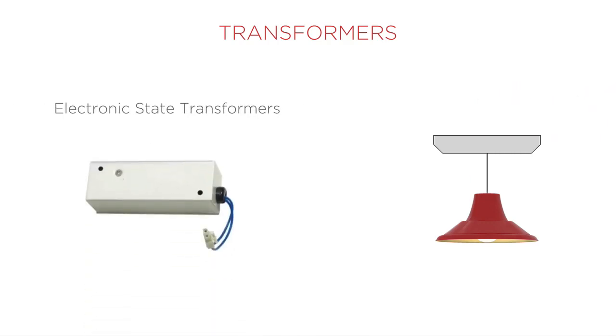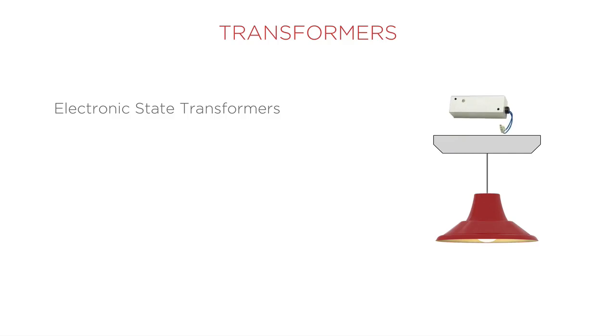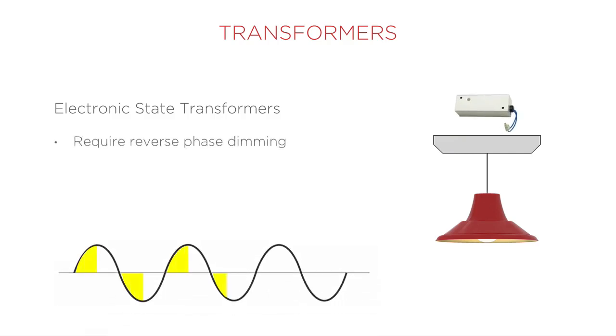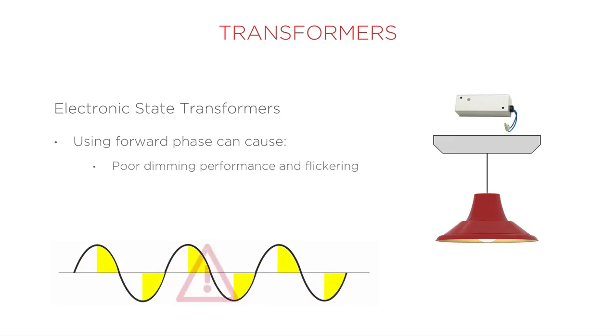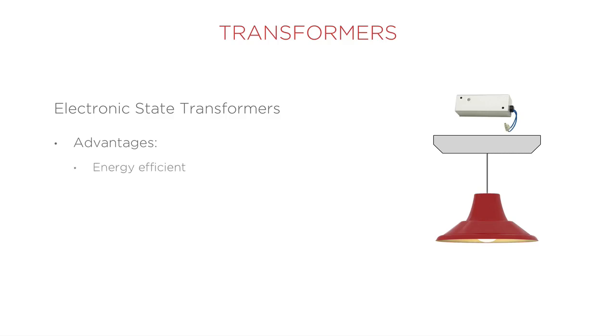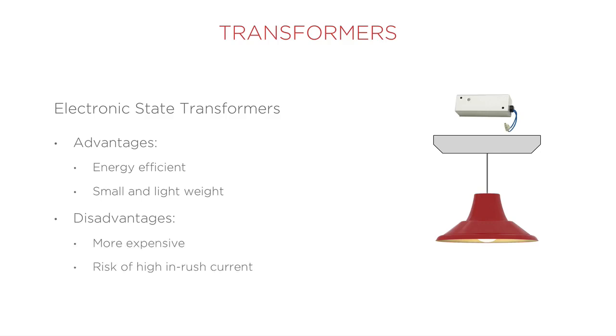Electronic state transformers are the newer type of transformer. They require reverse phase dimming. If used with a forward phase fixture or load, there will be poor dimming performance and flickering, buzzing from the bulb itself, and damage to the dimmer and/or the transformer. It is more efficient, smaller, and lightweight than the older magnetic core transformers, but they are more expensive and they have a risk of high inrush current.